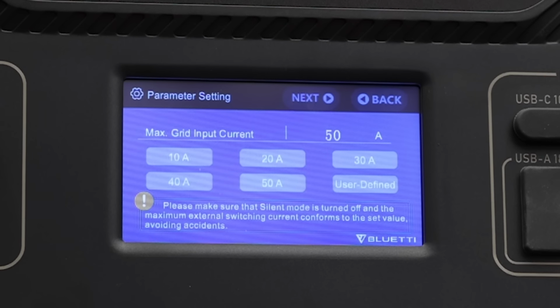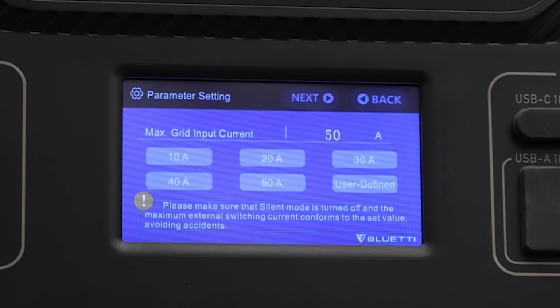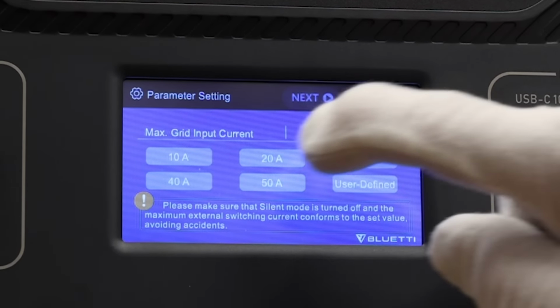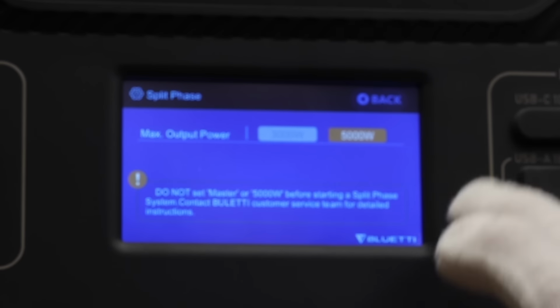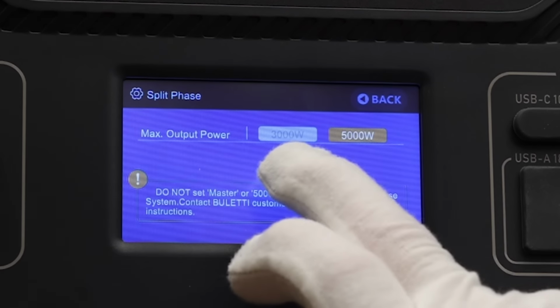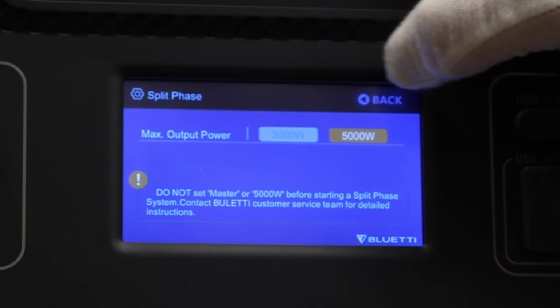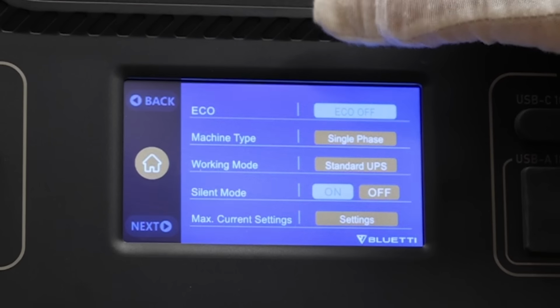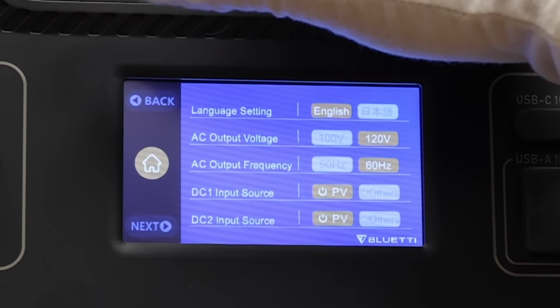Once you put in the secret password, you get a new screen giving options from 10 amps to 50 amps. I set it to 50 amps, and on the next screen you can limit the maximum output power. If for some reason you want to set it to 3,000 you can, but I'm setting it to 5,000 because I'm maxing this thing out for my tests. We have that completely set up.